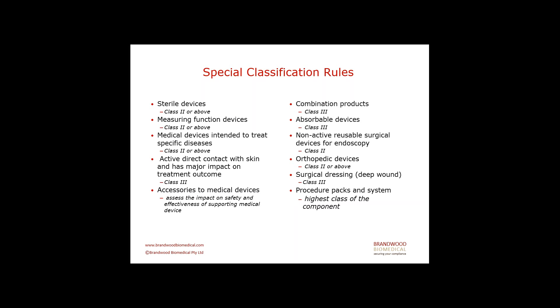For combination products, which are a combination of medical device and medicine, if the mode of action is medical device, the classification should be class 3. Absorbable devices are class 3 devices in China, and orthopedic devices are class 2 or above. For surgical dressings that treat deep wounds and contact injury to the deep dermis or below, or chronic wounds, or that can be entirely or partially absorbable, you will consider them class 3 in China. For procedure packs and systems, the classification is the highest class of the components within the kit.